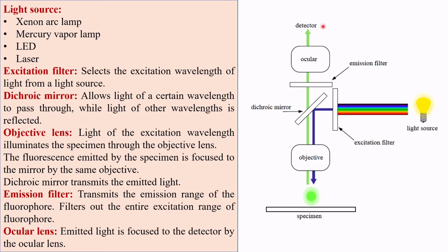Now in fluorescence microscopy, you have a particular fluorophore you are using in this sample, right? A particular fluorophore gets excited by a specific wavelength of light and also emits a specific wavelength of light. So you know those wavelengths before starting your imaging. Now you set the particular excitation wavelength that will be passed.